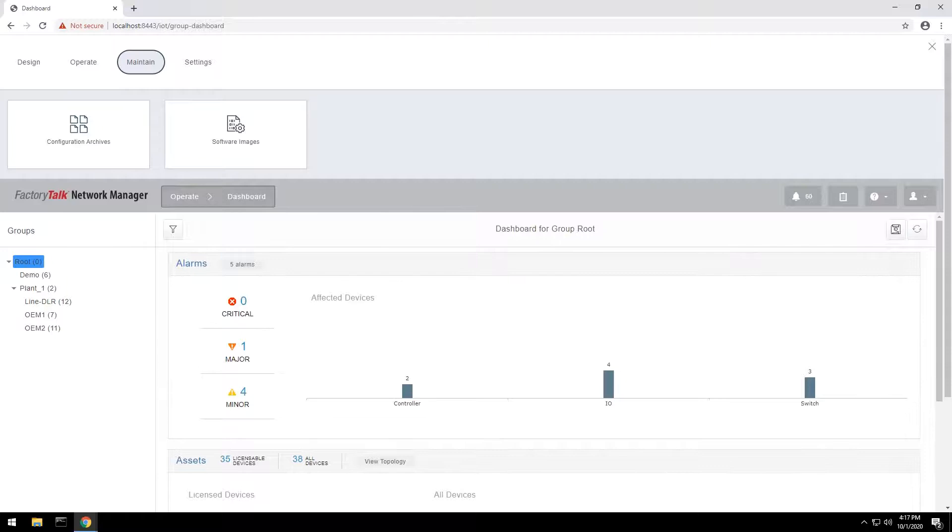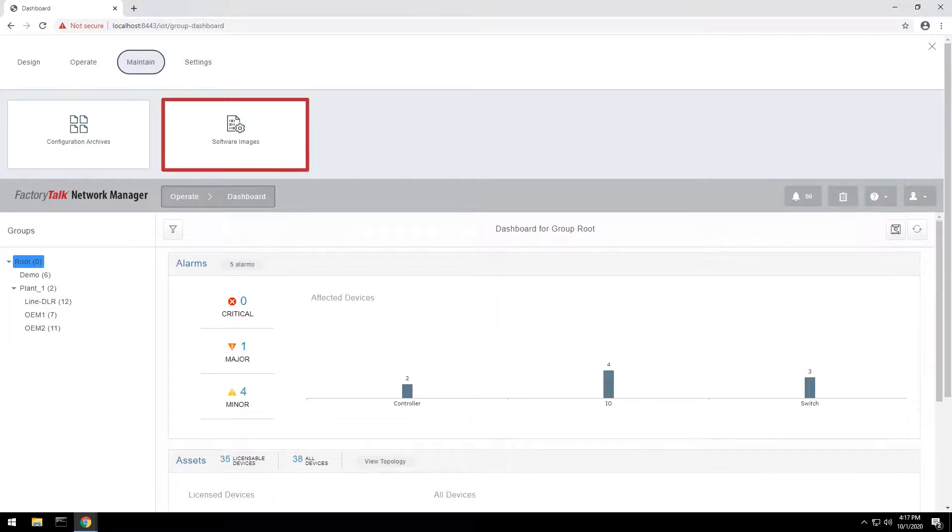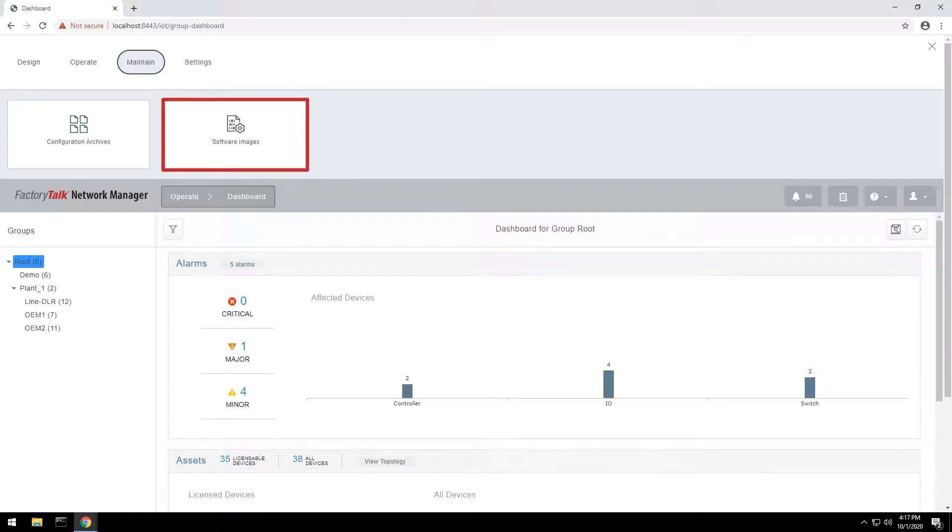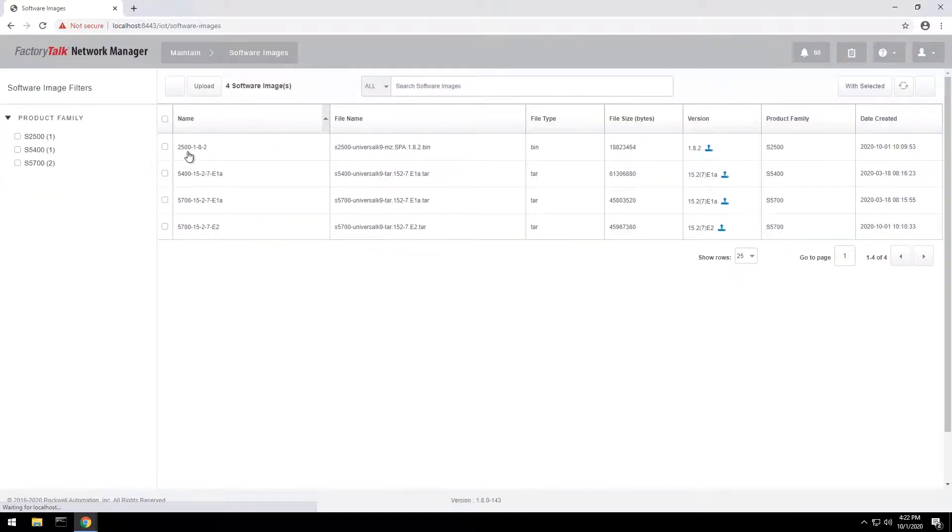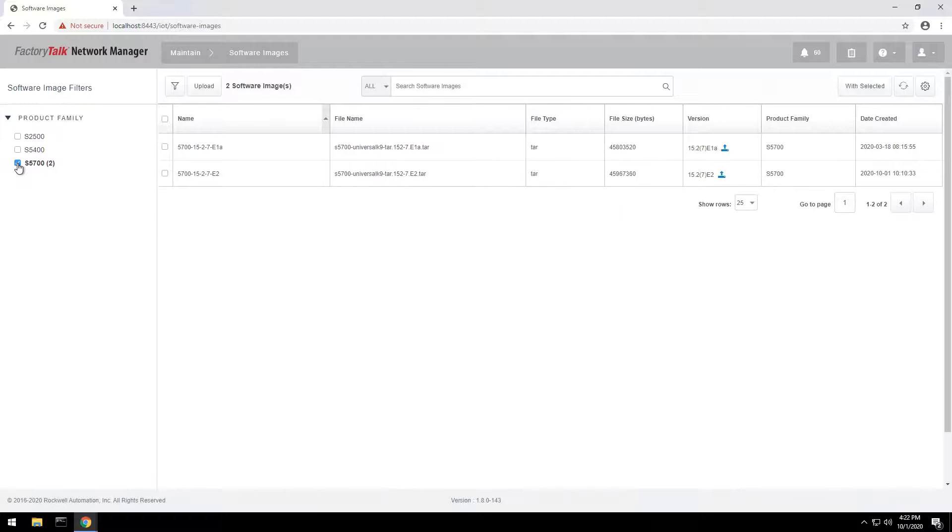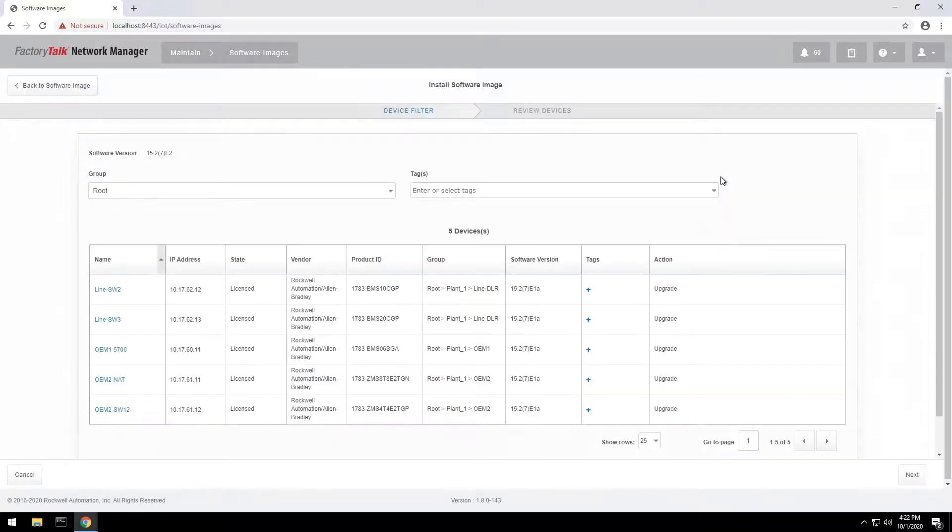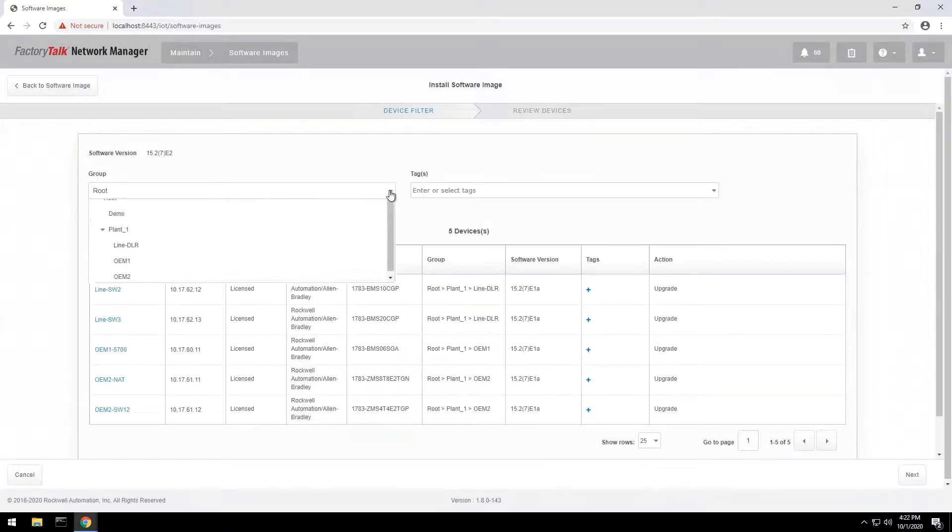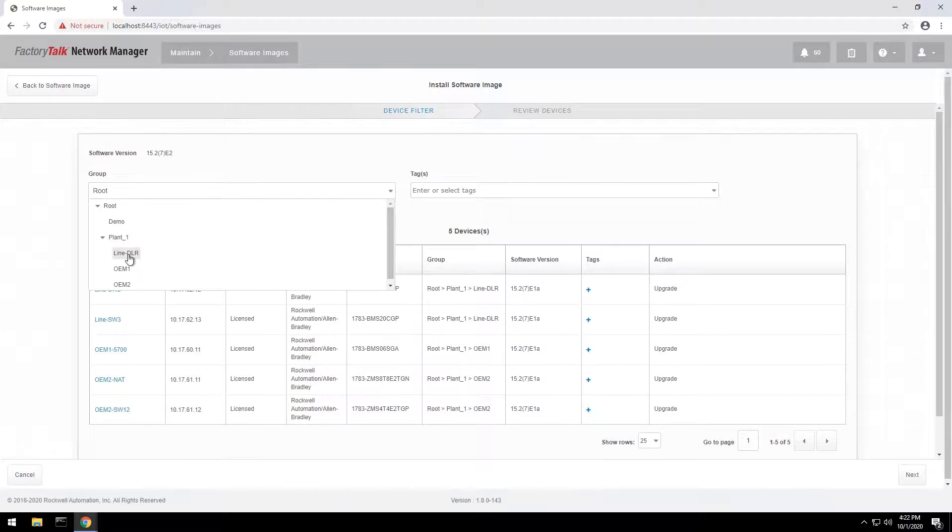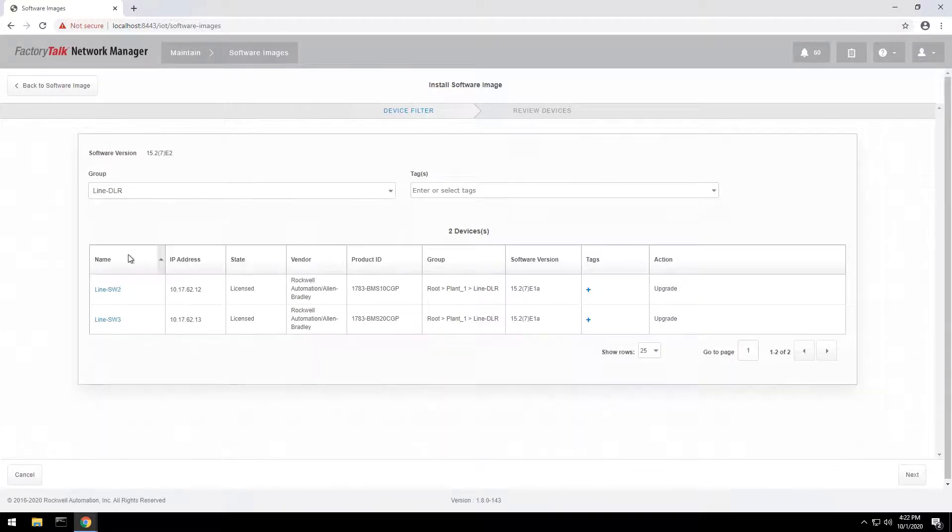Managing and upgrading switch firmware is an important but time-consuming task. FactoryTalk Network Manager reduces time needed to upgrade a large number of switches, minimizing the required maintenance window. Multiple versions of firmware can be uploaded and stored on the server. After selecting the switch platform and firmware version, you can see the list of switches that can be updated. The list can be filtered by device group, which for example can be a production line or a machine.